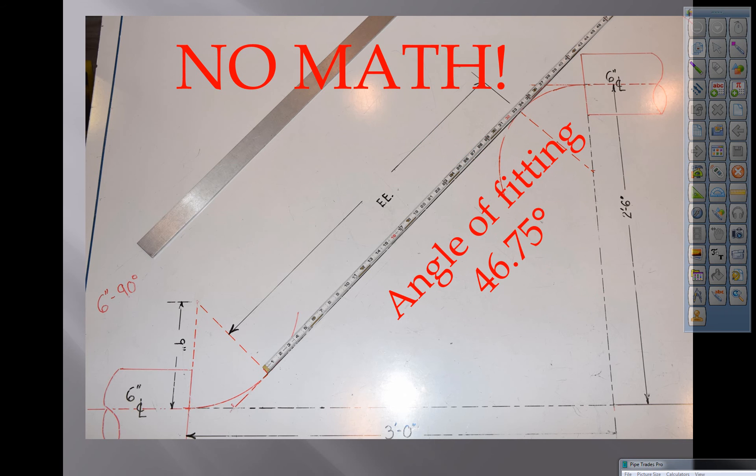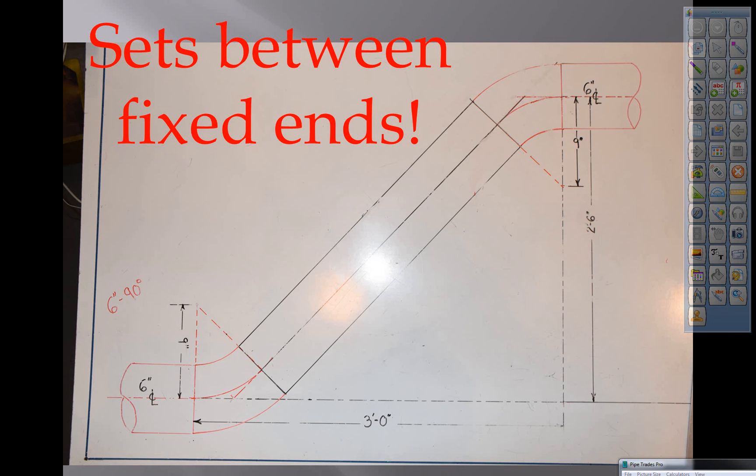46.75 on the fitting. 3 and 7 eighths for the takeoff. We read the rule. We take off an eighth inch gap. And we have 2 foot 9 and 3 sixteenths. So there you have it. It sets between fixed ends. And you're ready to go.